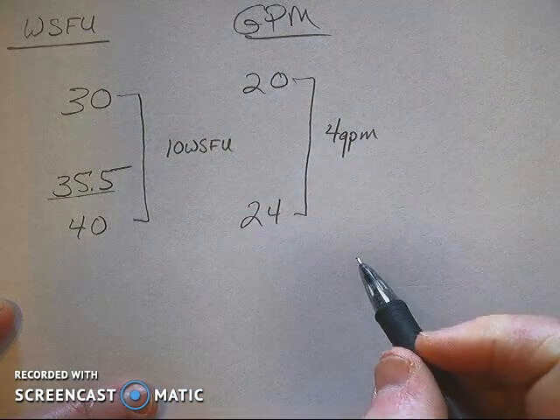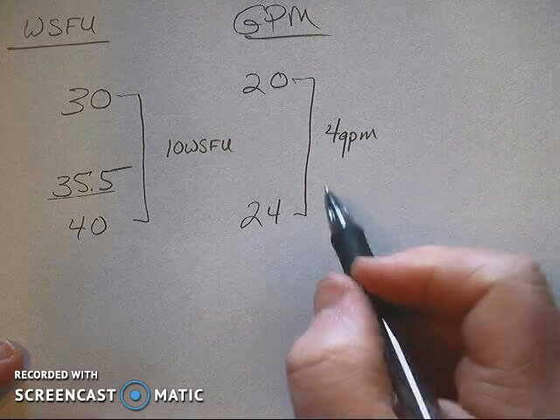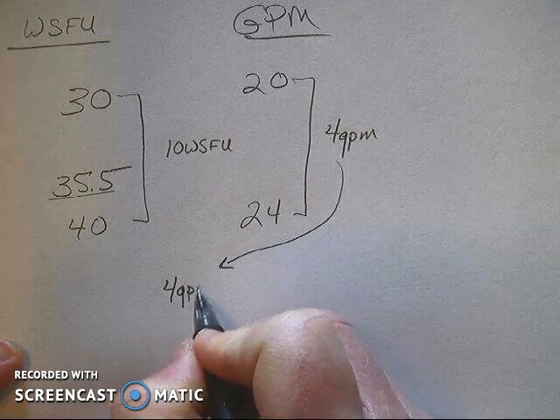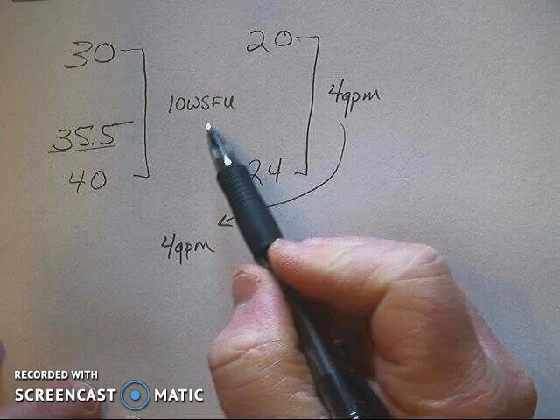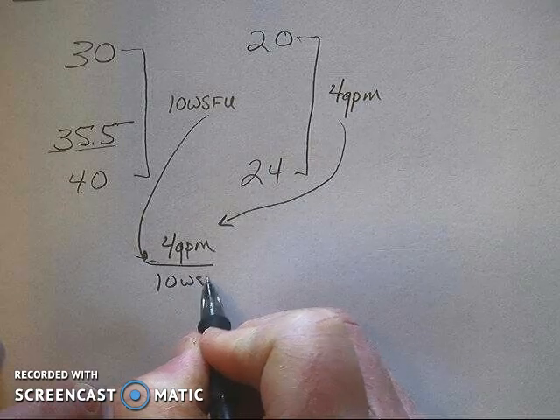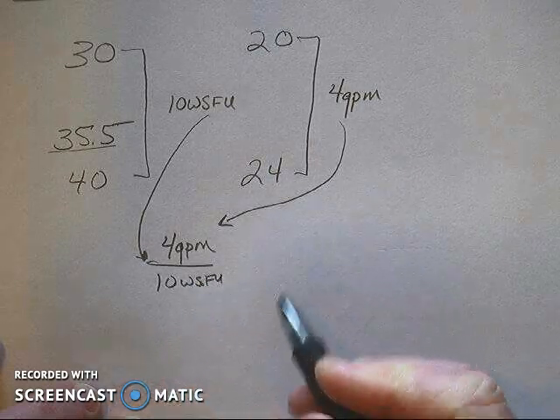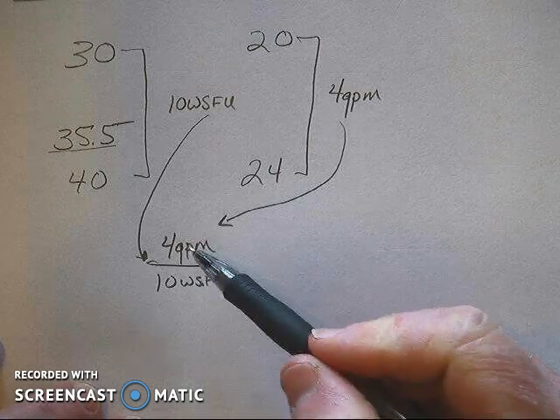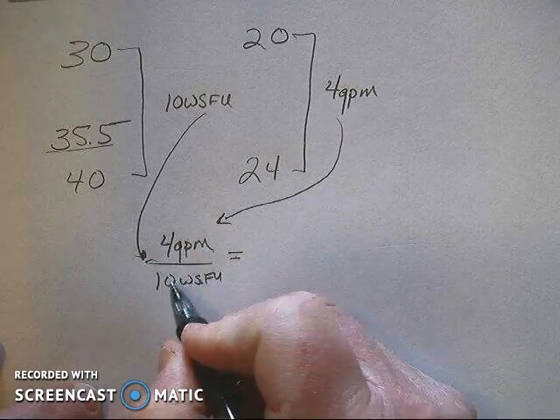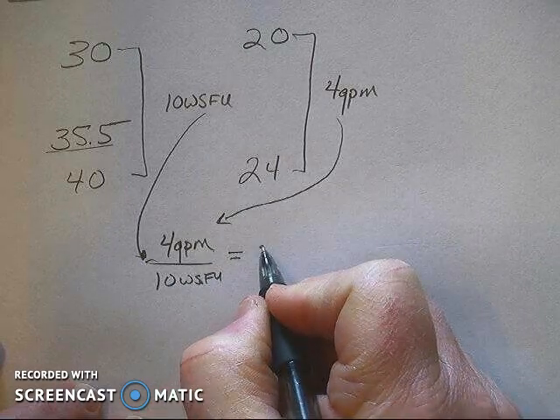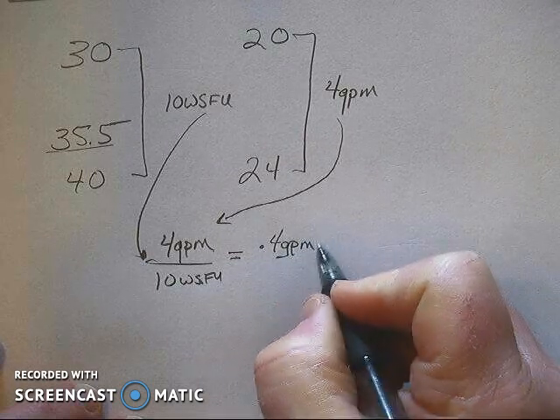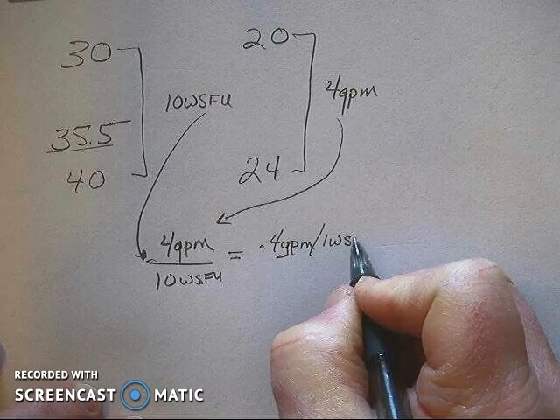With those two numbers I'll set up an equation. I'll take my 4 GPM and put it here and then I will take my 10 WSFU and put it right here and I'm going to divide the 4 GPM by the 10 WSFU. Now I'm going to label it gallons per minute per one WSFU.